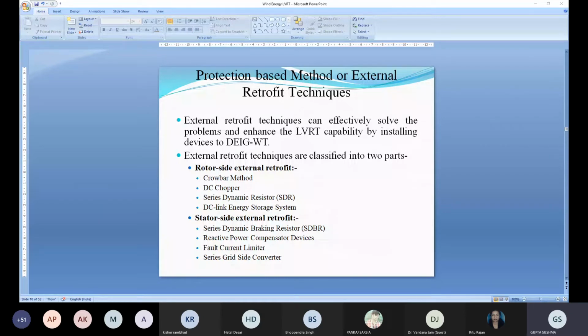In the crowbar method, I think you know the crowbar method. In the crowbar method, we connect a resistor. The crowbar circuit consists of a parallel resistance installed in the rotor winding and the AC side of the rotor side converter. Basically, in the crowbar circuit, we connect a resistor through a diode rectifier and an SCR. When there is a fault in the grid, we have an inrush current at the rotor side and we get more current.